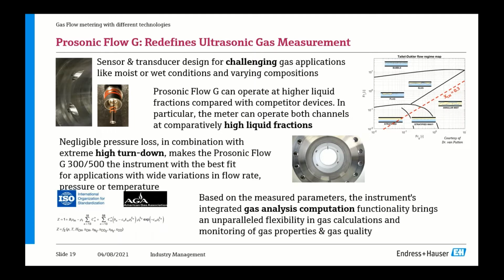And this capability to measure moist or wet gas, we can really see back in the capability to measure high liquid fractions. The figure on the top right explains a bit the area where we are working with this device. We say this device can measure reliably up to a Lockhart-Martinelli of 0.3, and that is something which you don't see often in the industry. A typical ultrasonic flow meter cannot do this, and the same you can say for actually all the other measuring principles. Maybe the best alternative you still have is a DP solution with a Venturi. But also with the Venturi, you have, for example, a problem with the turn down.